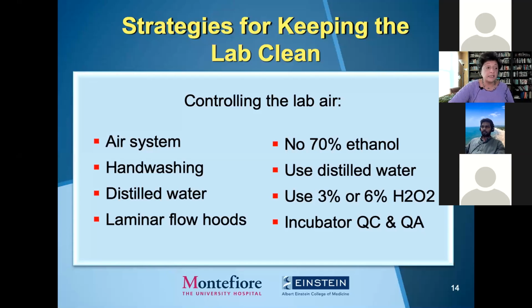Reduce or ideally eliminate the use of 70% ethyl alcohol or ethanol when cleaning surfaces. The level of alcohol measured varies from lab to lab. Alcohol used to wipe down surfaces becomes airborne, introducing VOCs into the lab air, which can deposit into your air filtration system. Instead, clean lab surfaces regularly with distilled water and decontaminate with hydrogen peroxide, either at 3% or 6% concentration.